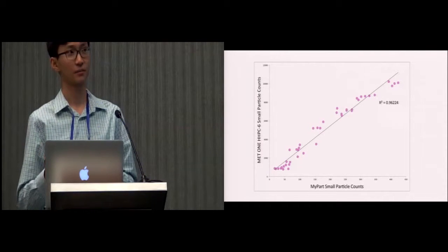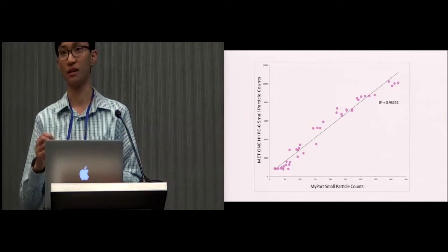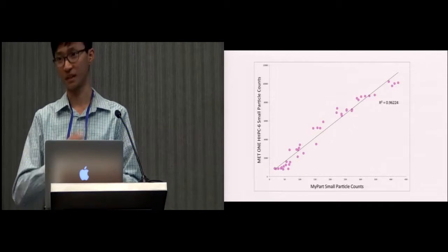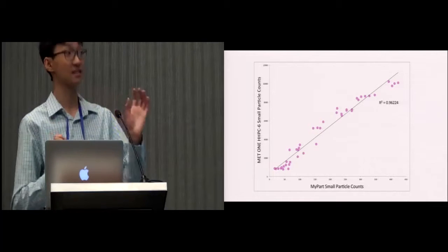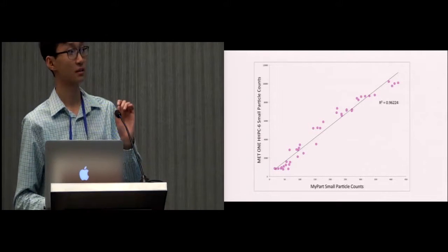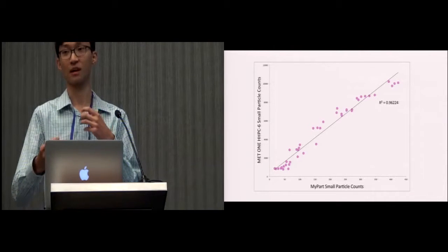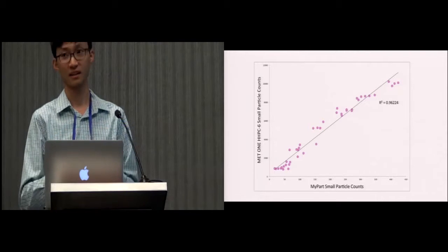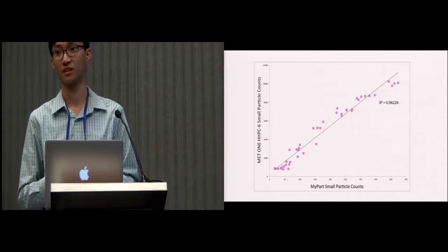To really calibrate that sensitivity well, what you would have to do is get a test chamber and then release particles of exactly known distributions. So this is an open ambient environment test? Right, that was the purpose of this test, to test it in these ambient environments that range from indoor and outdoor locations, to see if the light leakage was an issue or if the different sunlight conditions were an issue.